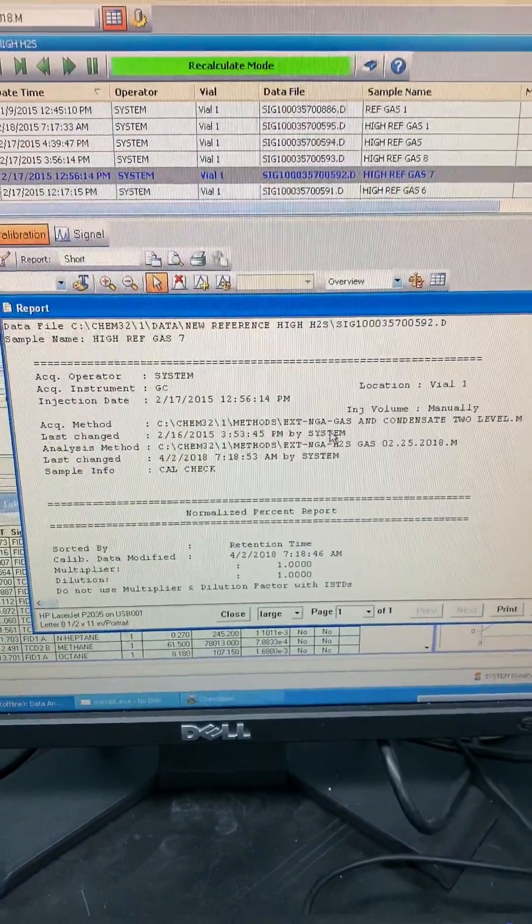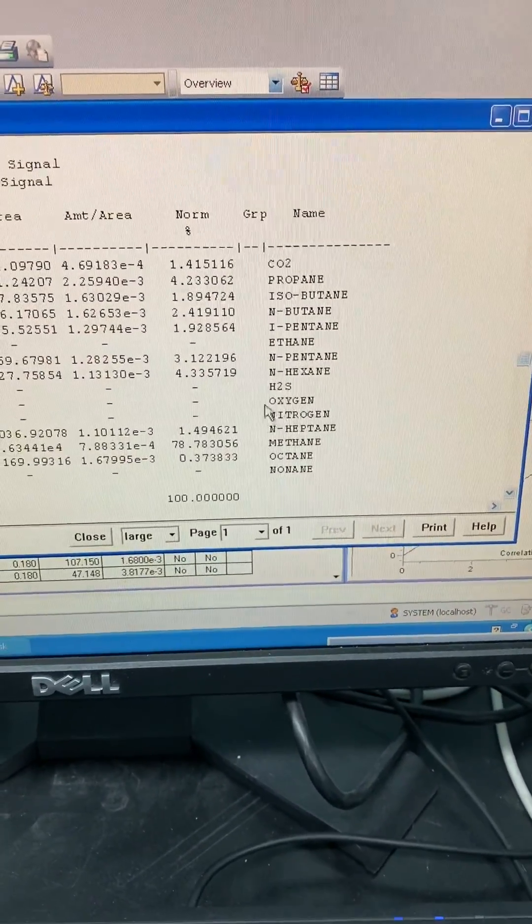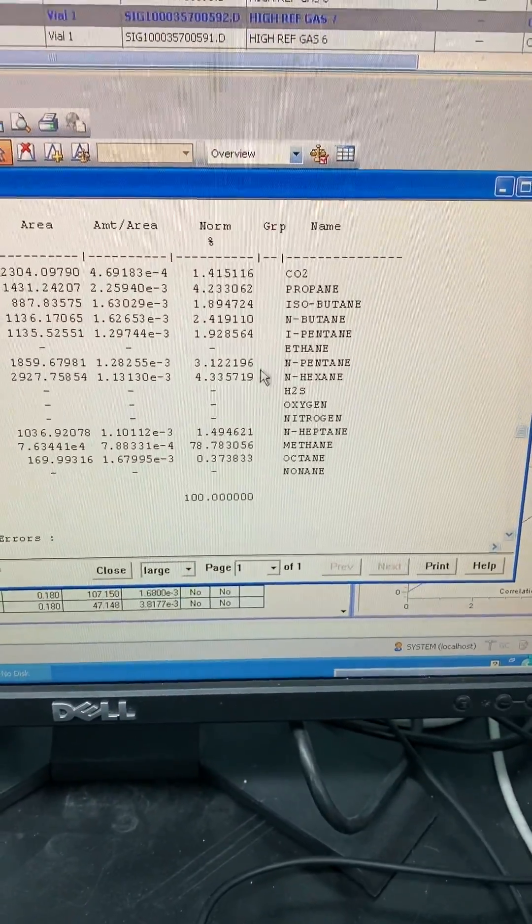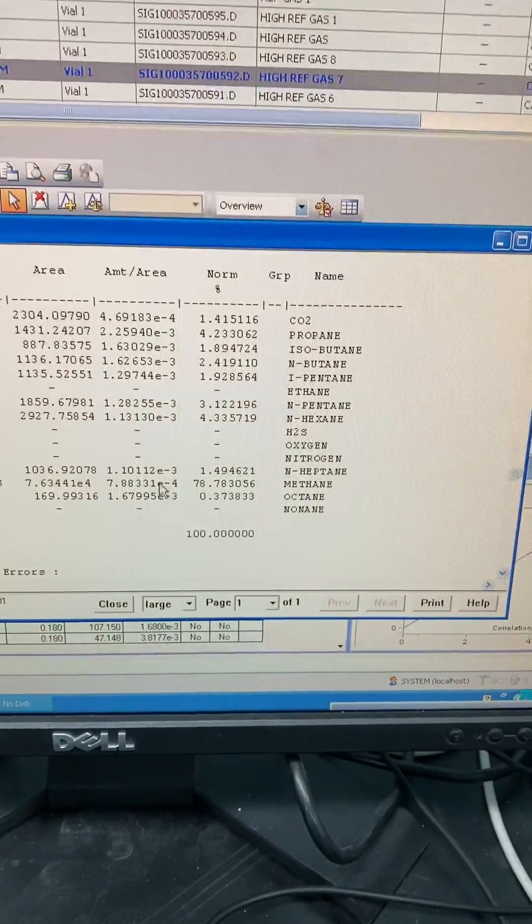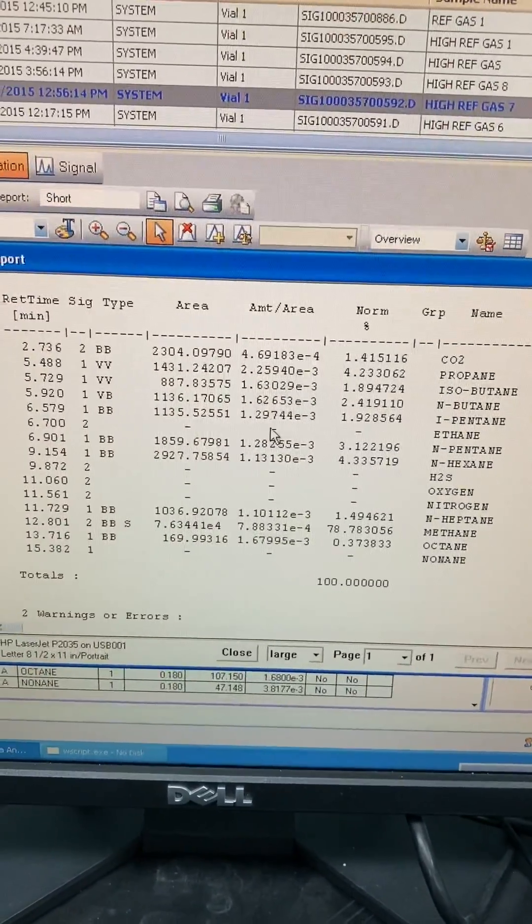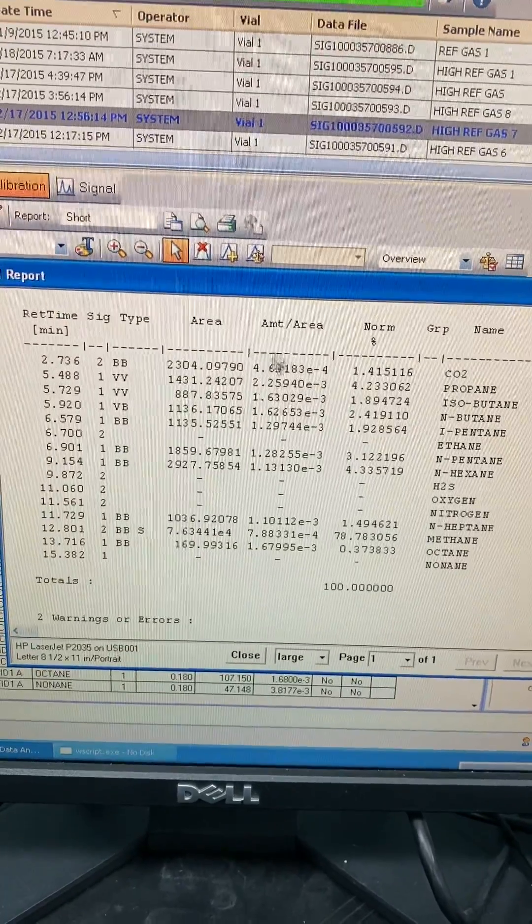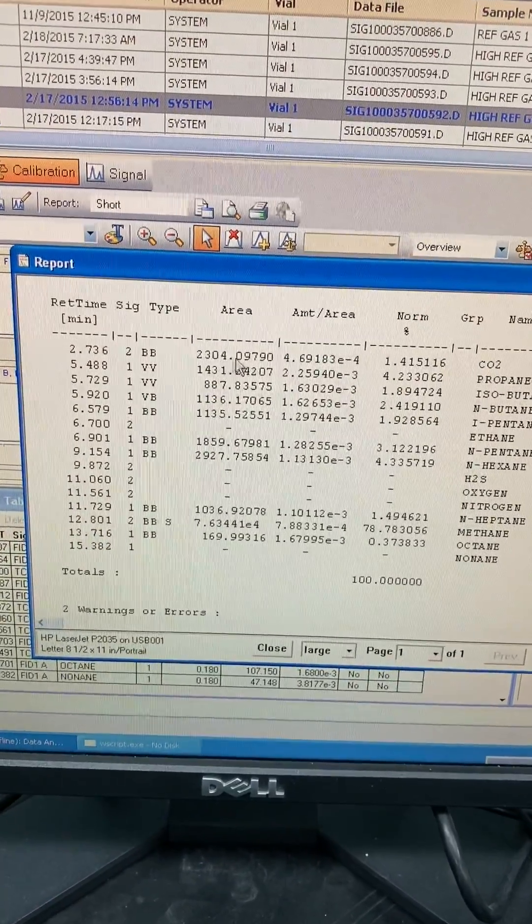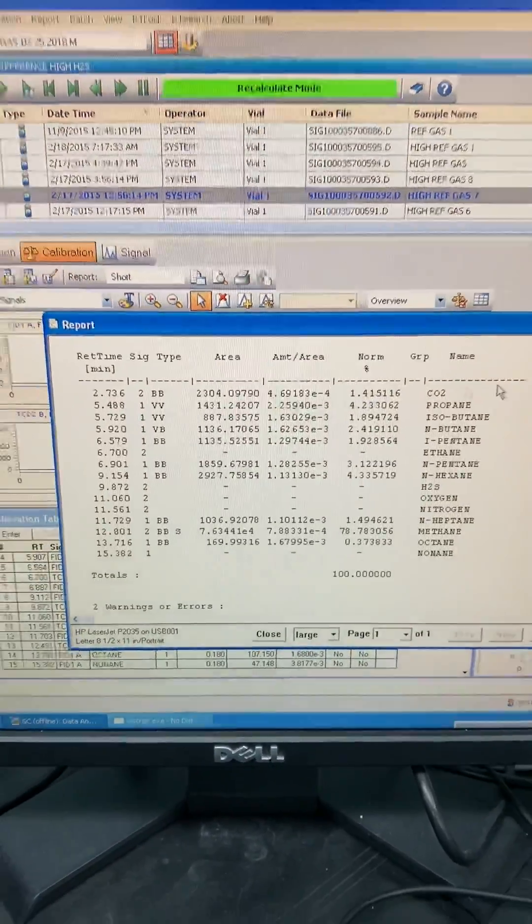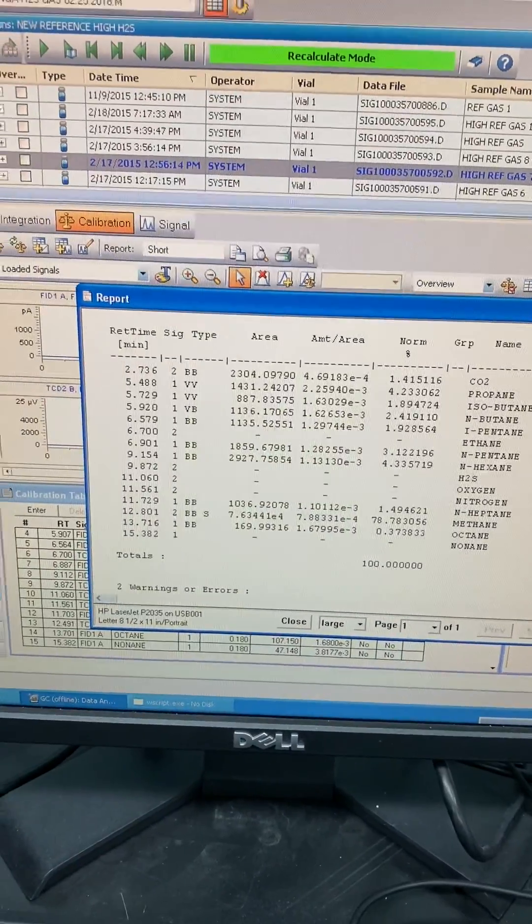Like having the final report, you will see some peaks will be identified, and the other ones are not identified. Like here, you can see the H2S, oxygen, nitrogen, all are missing, and also ethane. However, the result is already normalized to 100%. Here, the amount, on the peak area, this is like the response factor, and here are the area. You have to compare between each run and the other one for the areas, if they are matched or not matched together.